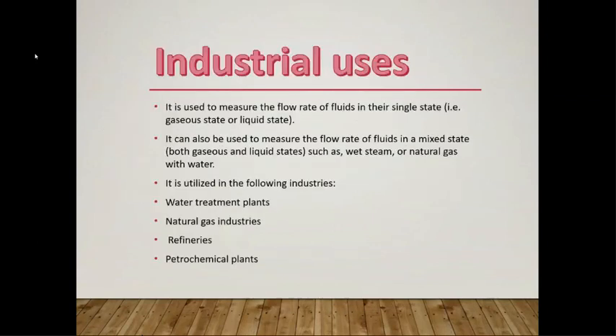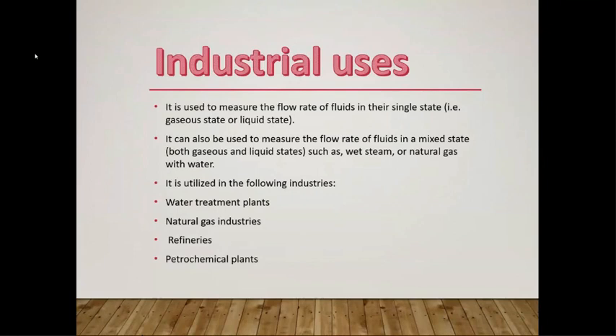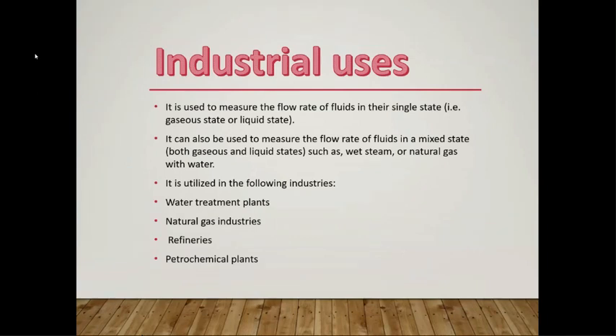As chemical engineering students, we must know the industrial uses of this experiment. The orifice plate, called a calibrated orifice, is used to measure the flow rate of fluids in single states — gaseous or liquid — and also in mixed states such as wet steam or natural gas with water. It is used in various industries including water treatment plants, natural gas industries, refineries, and petrochemical industries. Orifice plates are also used to reduce pressure or resist flow, in which case they are called restriction plates.